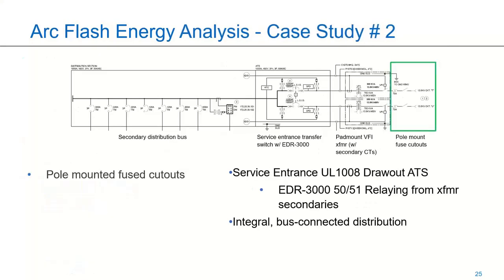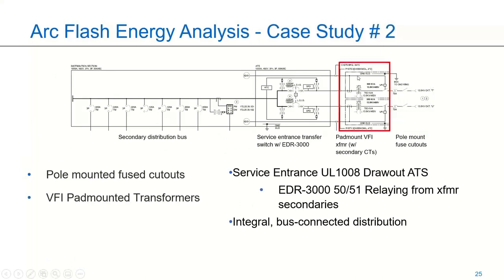Looking at their single line, in this case you had the pole-mounted fuse cutouts. This is the utility portion right here, and then feeding, now slightly more integrated than last time, we've got our pad mount transformer with secondary CTs like we did in case study one. But in that pad mount transformer, we also have a vacuum interrupter. We have a trippable device. So instead of an upstream recloser that we're tripping, we've now got a consolidated piece of equipment: transformer, vacuum interrupter, as well as those secondary CTs. However, in this case, we do still have the relaying portion in the downstream gear.